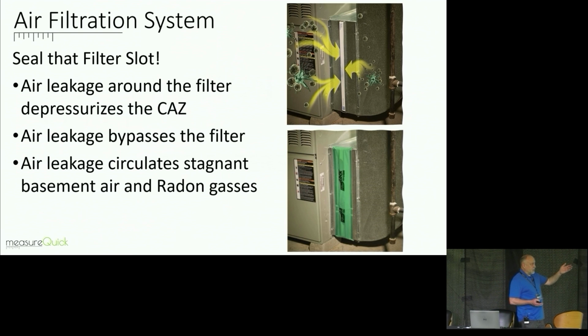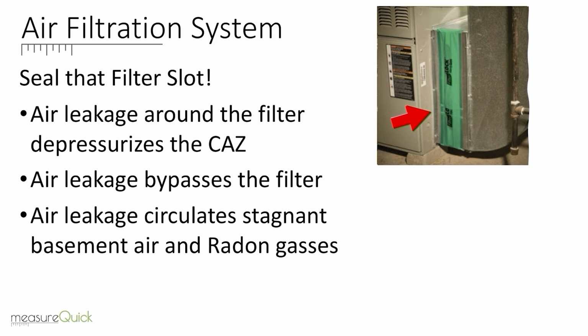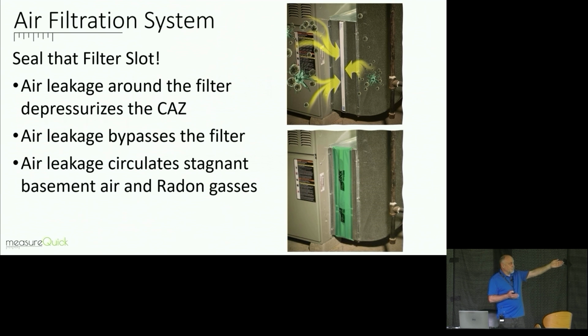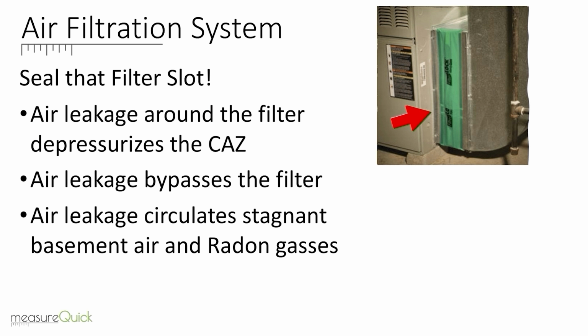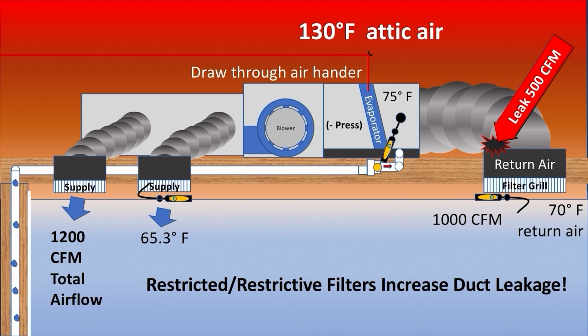And the filters on our systems were not that great. And I don't know how many times I've seen, in our market, the one David and I are from, open filter slots in the basement. The filter doesn't care, or that slot doesn't care which side of the filter is pulling air. It doesn't say, you know what, the filter is on the left, so please pull all the air from the left side. It pulls it from whatever side it can. Sealing up that filter slot and getting rid of the CAZ depressurization, getting the air to stop bypassing the filters, is of critical importance. And this one here is an interesting thing. A lot of times we'll see the homeowner will go out and buy the 3M filter, and nothing gets through the filter, including air.